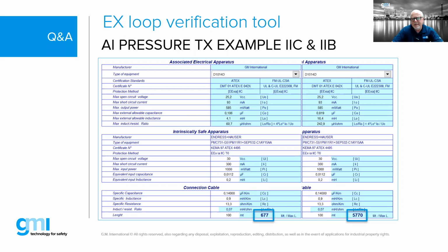So what that's telling you is that if we're putting this into an environment where acetylene or hydrogen is present, a 2C environment, the length of cable run based on the capacitance and inductance is much, much less than what we can achieve for normal 2B or even 2A gases.